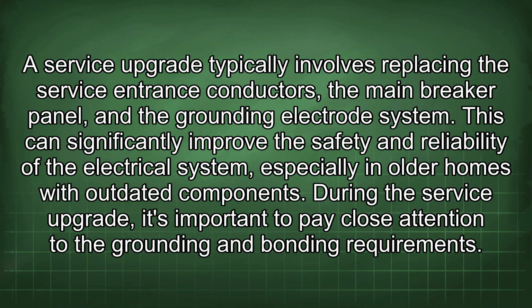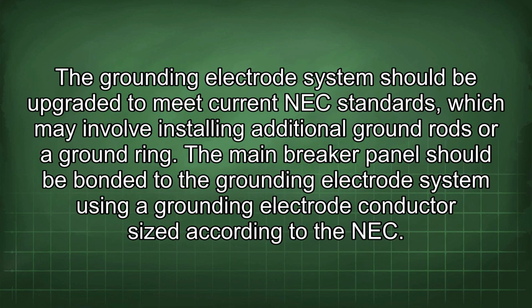A service upgrade typically involves replacing the service entrance conductors, the main breaker panel, and the grounding electrode system. This can significantly improve the safety and reliability of the electrical system, especially in older homes with outdated components. During the service upgrade, it's important to pay close attention to the grounding and bonding requirements. The grounding electrode system should be upgraded to meet current NEC standards, which may involve installing additional ground rods or a ground ring. The main breaker panel should be bonded to the grounding electrode system using a grounding electrode conductor sized according to the NEC.